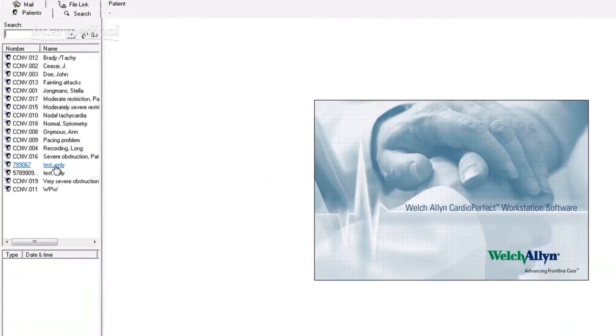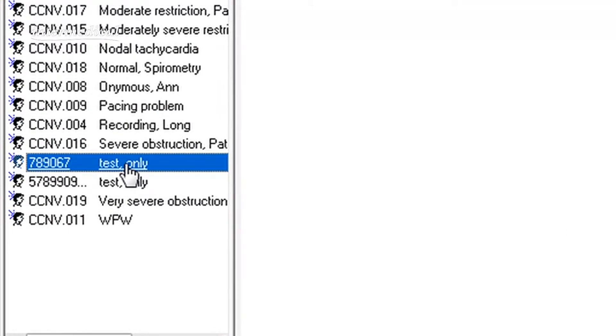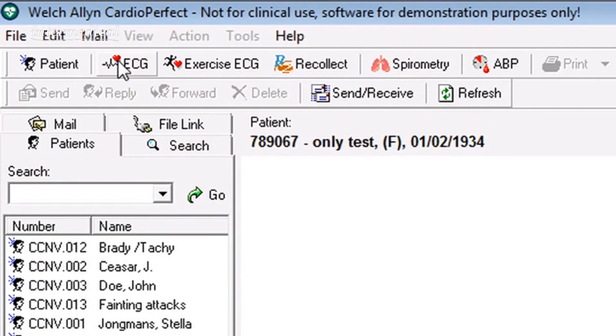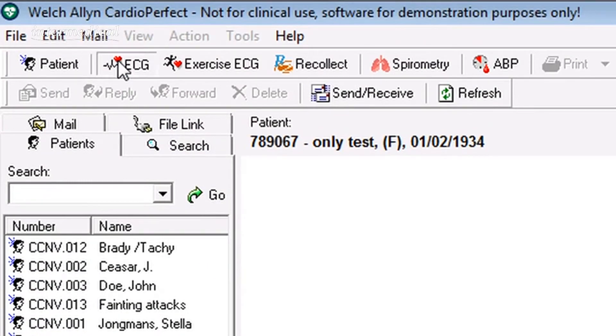So that's the resting ECG. But what if you want to take a longer ECG, a rhythm ECG? Well, for this, you need to go back into the software and again, either input or find your patient, highlight their name, and again click on the ECG icon at the top of the screen.